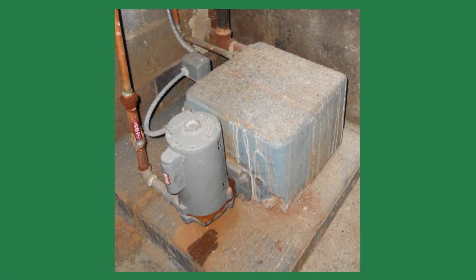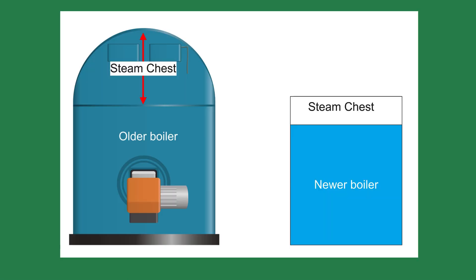Many older boiler plants use the condensate tank to return condensate to the boilers. The old boilers had large steam chests and the water level is not critical. The new boilers have smaller steam chests and the water level is absolutely critical, so a condensate tank will not work with the newer boilers.